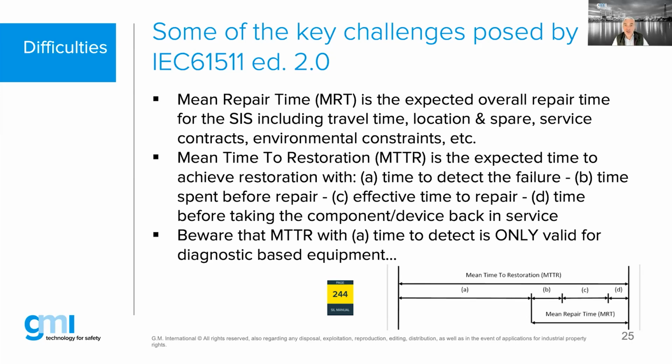When you find the failure, we call that you reveal the failure. We don't say you detect the failure. Detection is by built-in diagnostics. It's done automatically by the manufacturer's built-in intelligence, and they can provide you with a safe solution, going potentially to a safe state. For example, when you have a safety PLC with diagnostic coverage on the digital output module, and this digital output module would not be able to shut down the output channel, then the diagnostic needs to have a secondary means to remove the power to the field so that you can go to a safe state. That's a clear example of a safe decision based on a dangerous detected failure.